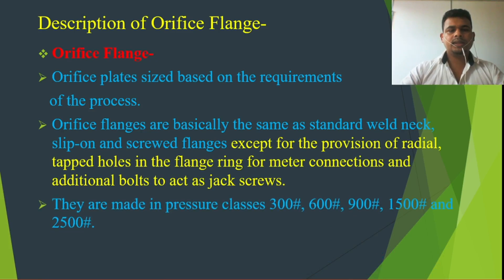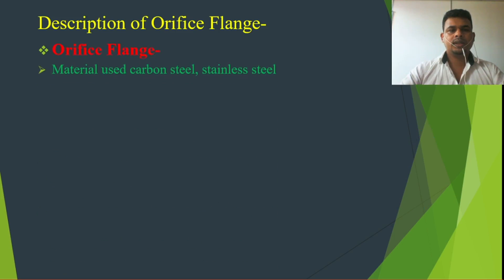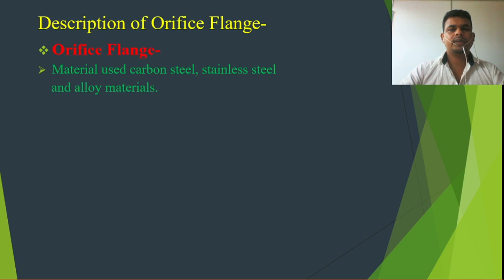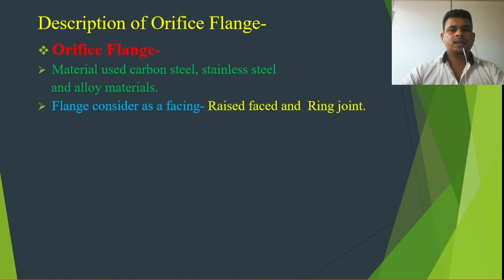Orifice flanges are made in pressure classes 300, 600, 900, 1500, and 2500. For materials, carbon steel and alloy steel materials are used. Regarding flange facing, we can see there is raised face and ring joint facing available.